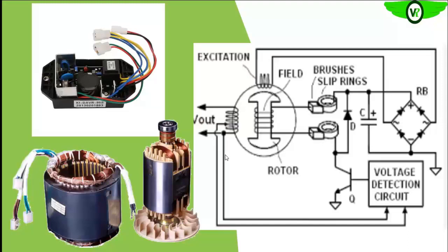take the reverse case, that is when you have overproduction of voltage, over-induction of voltage in the armature, this sensing lead will also get that signal of the overproduction. That will now be sent to the voltage detection circuit of the AVR. So seeing it as an overproduction, it will reduce the amount of voltage that will now be sent to the main field, which is this one now, okay?